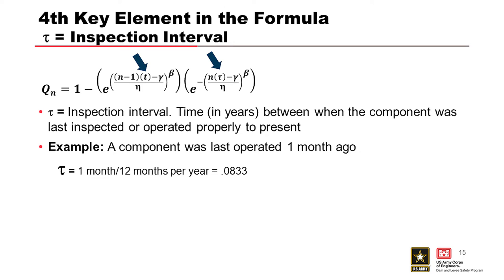And then the fourth key element in that dormant Weibull formula is the inspection interval. That's tau. It's time in years between when the component was last inspected or operated properly to present. We call it an inspection interval, but if it's operated, we typically say that that is the same as an inspection. So, it's inspection operation slash exercise interval.